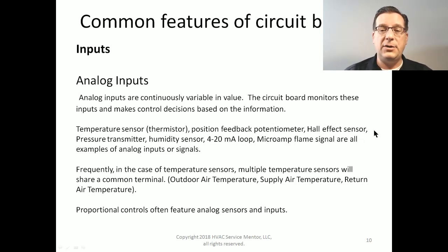A Hall effect sensor is a special type of sensor that identifies rotation. And the most common application for Hall effect sensors in HVAC is on commercial rooftop unit draft inducers, to identify, is the draft inducer spinning, and is it spinning at the right speed. There are potentially other uses for Hall effect sensors monitoring blower speeds and compressor speeds in variable capacity equipment as well. Again, this is something that is somewhat rare today, but it is on its way to the residential market as we speak.